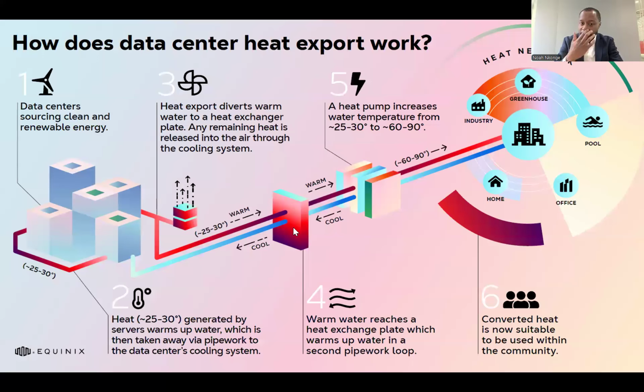I'll recap on what data center heat reuse looks like, focusing on the front end of the data center. When data centers power their customers' IT equipment, this generates heat, normally rejected to the atmosphere. With heat reuse, this heat is instead captured and transferred to pipework within the data center, then put through a heat exchanger where it's transferred to a third party, such as a heat network operator.